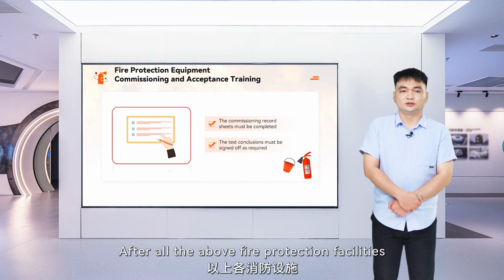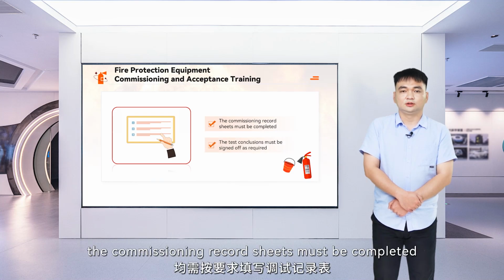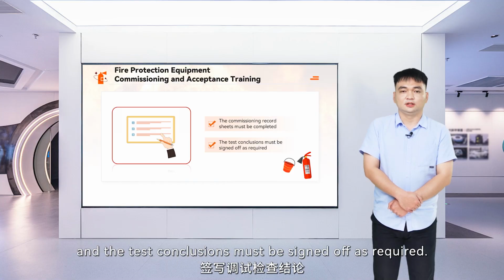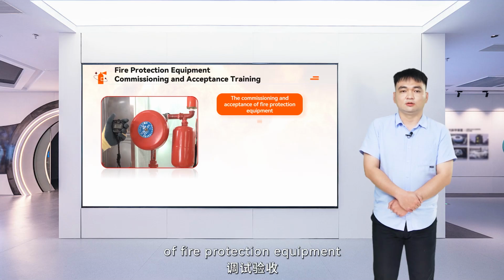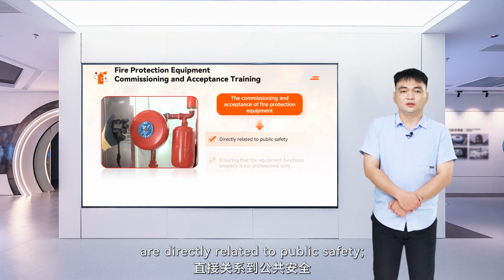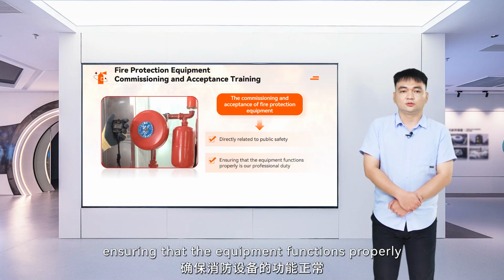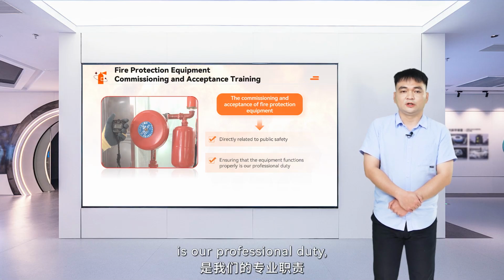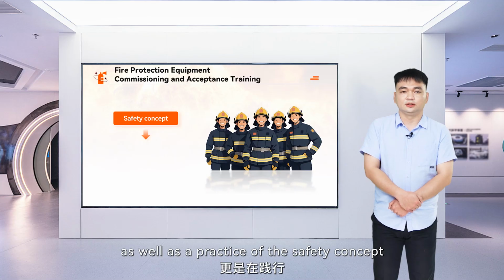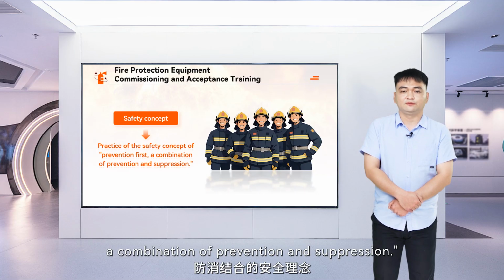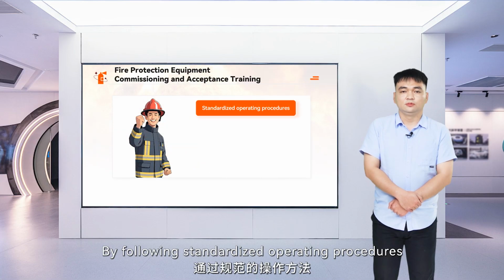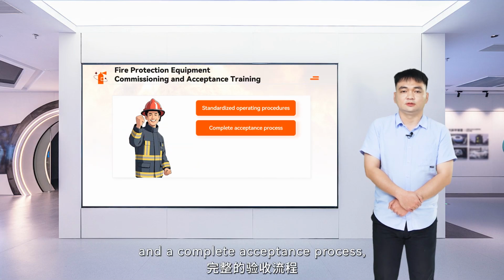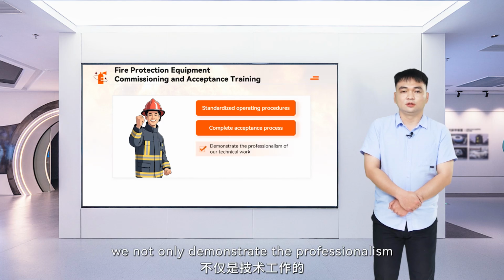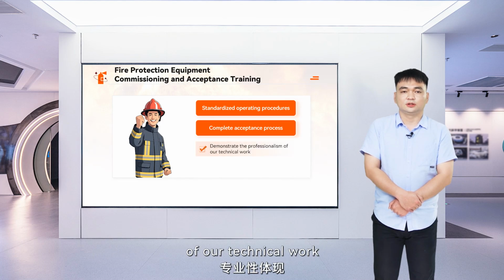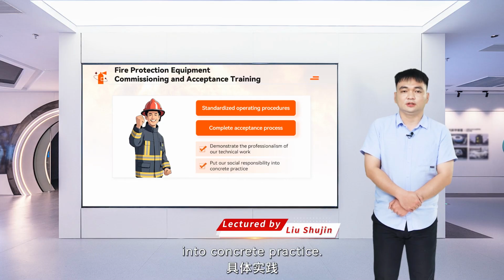After all the above fire protection facilities have been commissioned, the commissioning record sheets must be completed and the test conclusions must be signed off as required. The commissioning and acceptance of fire protection equipment are directly related to public safety. Ensuring that the equipment functions properly is our professional duty, as well as a practice of the safety concept of prevention first, a combination of prevention and suppression. By following standardized operating procedures and a complete acceptance process, we not only demonstrate the professionalism of our technical work but also put our social responsibility into concrete practice.